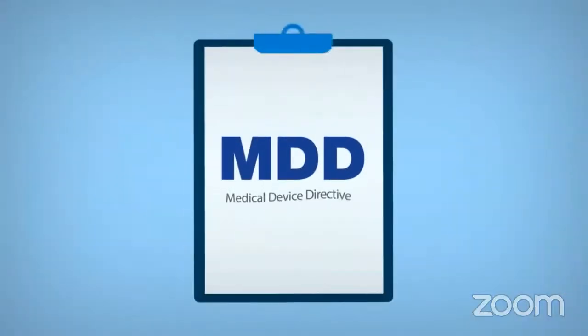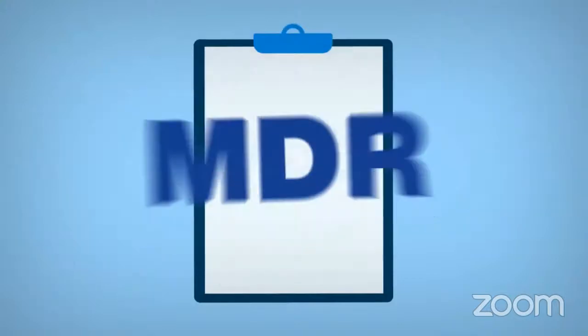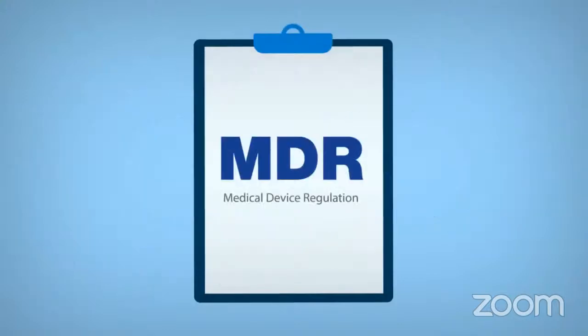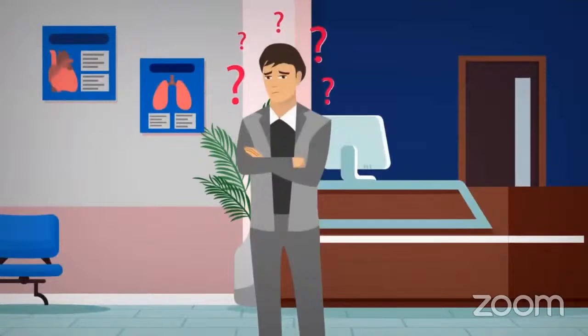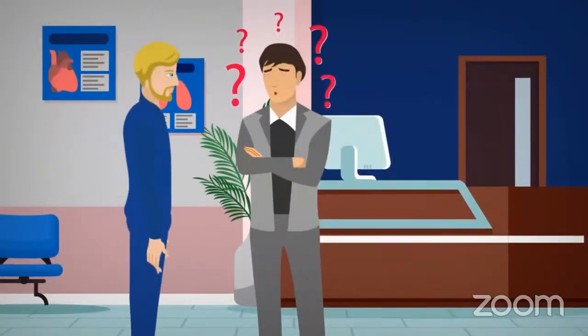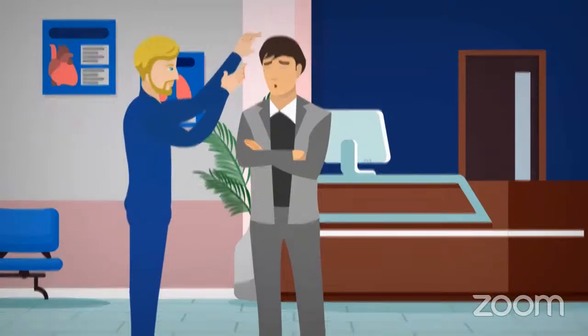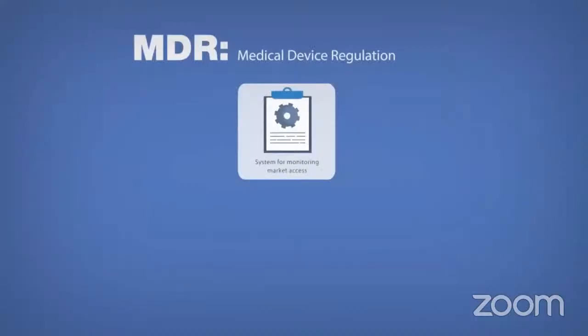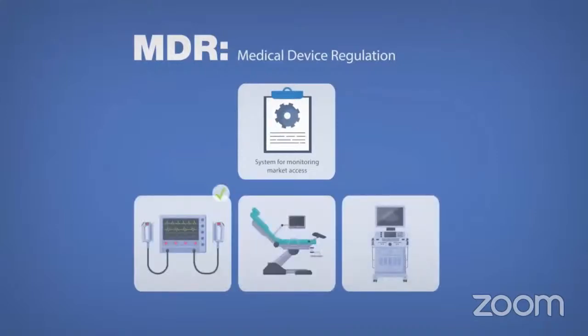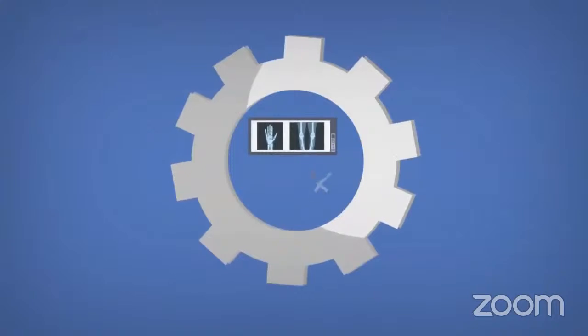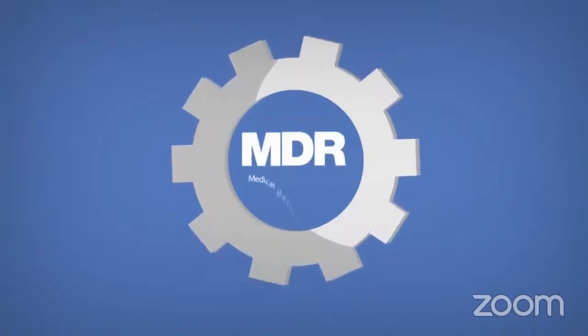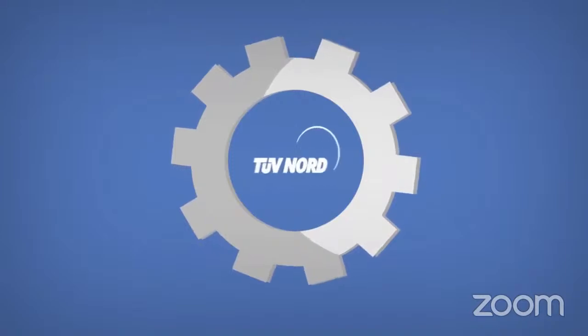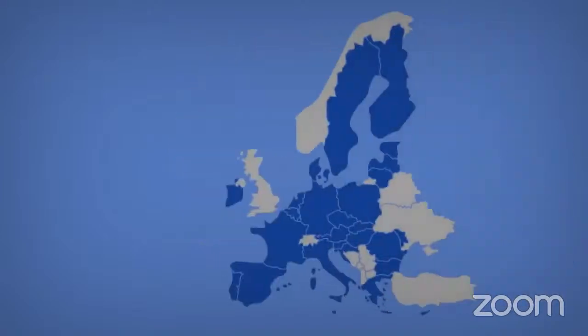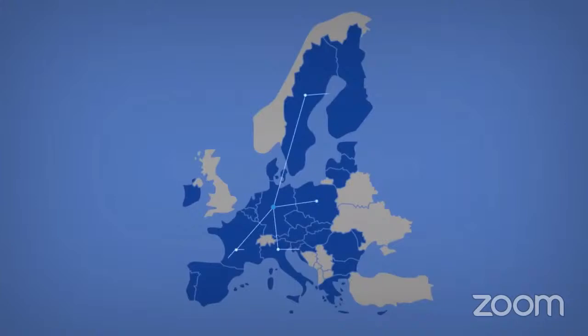The MDD, the Medical Device Directive, has been replaced by the MDR, the Medical Device Regulation. What exactly does this mean for you and your company? With the MDR, a new and more stringent system for monitoring market access comes into force. It ensures that medical devices are safe, effective, and can be better traced. Manufacturers therefore need to reassess their medical devices according to the MDR, or have them assessed by a notified body. Only then can they continue to sell them in EU countries.